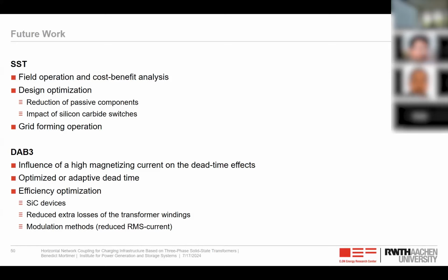So the efficiency of this dual active bridge was around 98%. So typically for IGBTs with 10 kilohertz, quite good, but still for grid applications, it might be a little bit too low if we compare it to a transformer, which is typically above 99%. And also some other modulation methods to have a reduced RMS current would also be of a high interest. And I can say we have work ongoing on that topic at this moment.